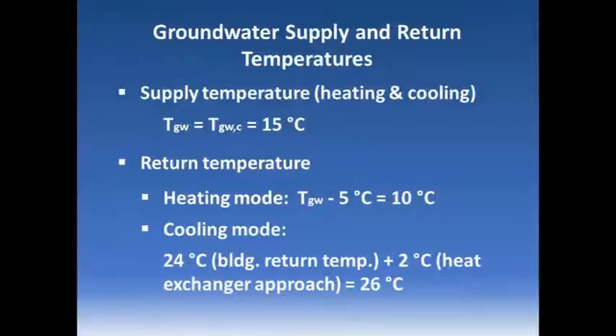The groundwater temperature we use is based on the data set from the Illinois Water Survey. For both heating and cooling cases, we used 15 degrees centigrade. And the return temperature is different. For heating mode, we use 10 degrees centigrade, which is the groundwater temperature minus 5 degrees C, based on the engineering design code. Generally, we let the temperature drop in the groundwater heat exchanger be about 5 degrees centigrade. And in the cooling mode, we use 26 degrees, which is the building return temperature, which we set as 24 degrees centigrade, plus 2 degrees, which is the heat exchanger approach.